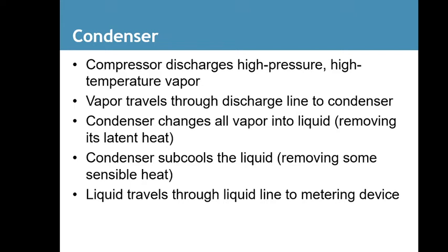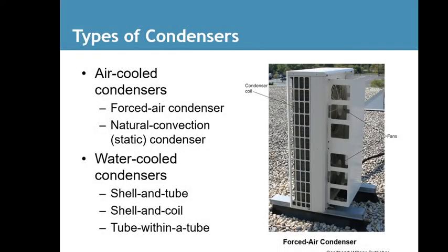And the subcool on this is very important. It's the only way to charge a unit that has a TXV. We went through this in class and we've had questions on it. But remember, it's just the gauge temperature before or after the condensing coil and the actual temperature on the liquid line after the condensing coil. Here's two types of condensers, air-cooled condensers and water-cooled condensers. In Florida, there are quite a few water-cooled condensers, but they're still considered rare.